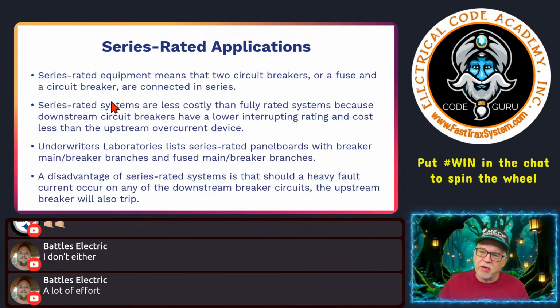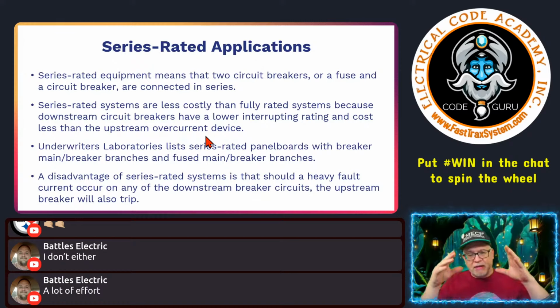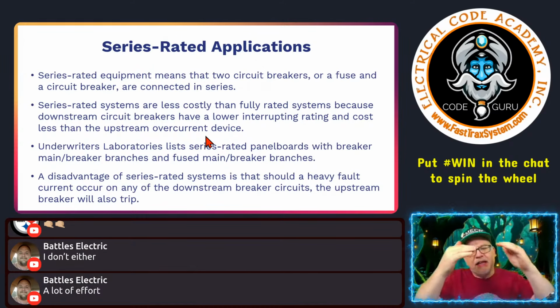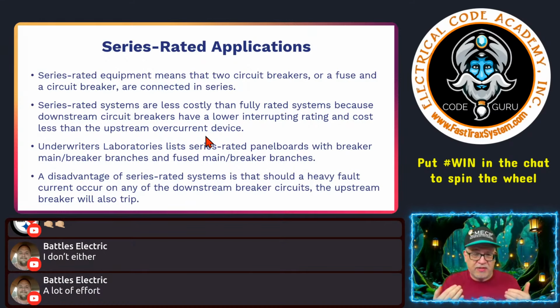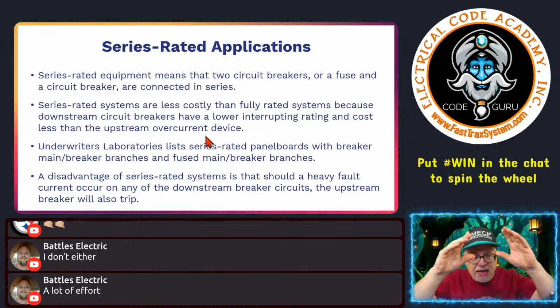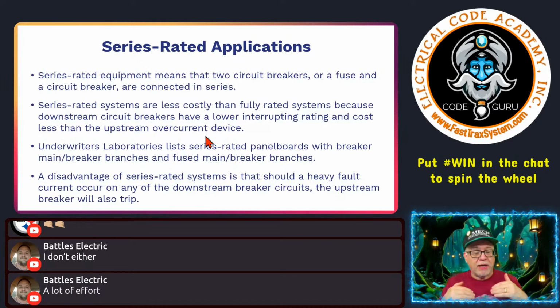So series rated systems are less costly than fully rated systems because downstream circuit breakers have a lower interruptive rating and cost less than the upstream. So this is how most of them are designed. It's a cascading effect. So this is what you'll get in a panel when you see your panel has a 22 KAIC main breaker, but then you'll see that each individual breaker is rated 10, let's say. Then you've got what's called a series rated system. Whereas it would be much more expensive to have a 22,000 rated main and have breakers that go in it that have to be equal to or greater than the rating of the main. That would be a much more expensive system because testing those breakers for those ratings would cost a lot more. It would be a lot more robust and that type of thing. So again, make sure you understand that, but most residential applications, even commercial, what you're dealing with is a series rating application. Okay.